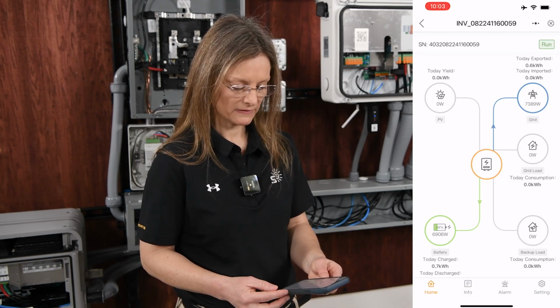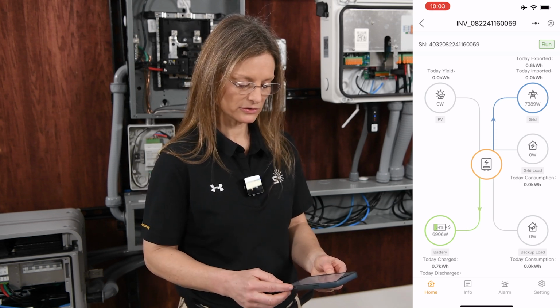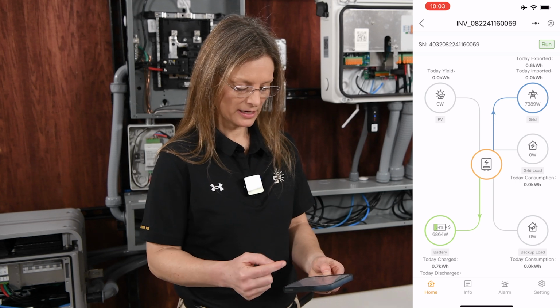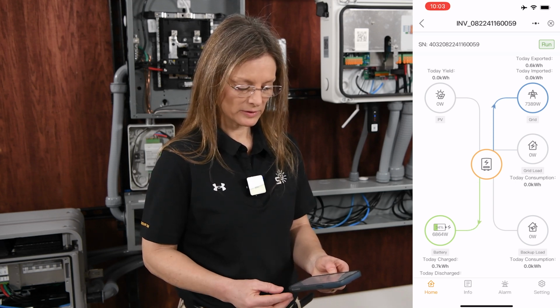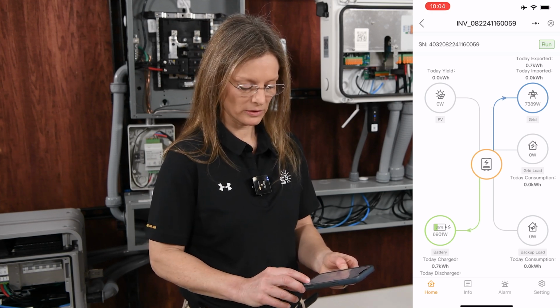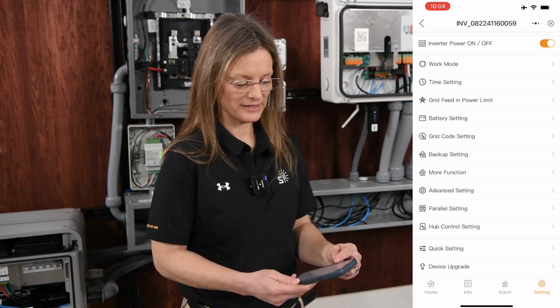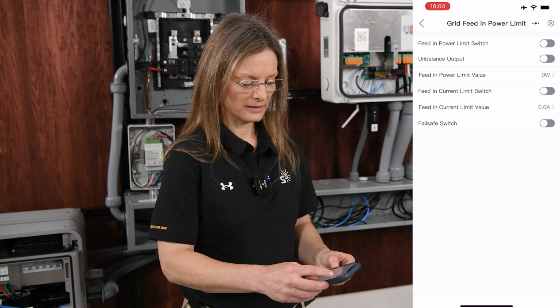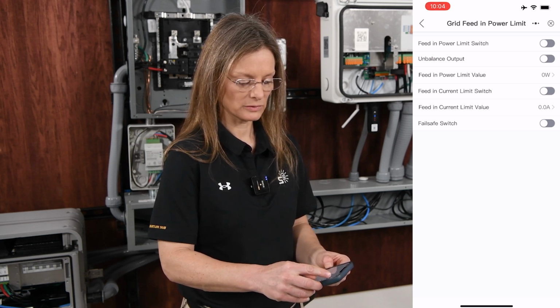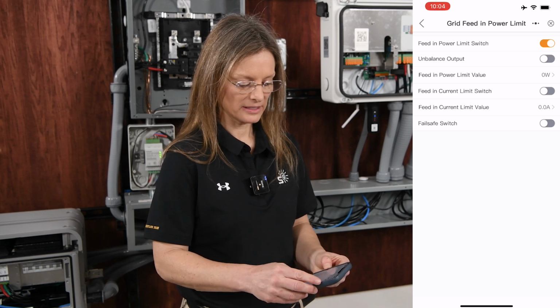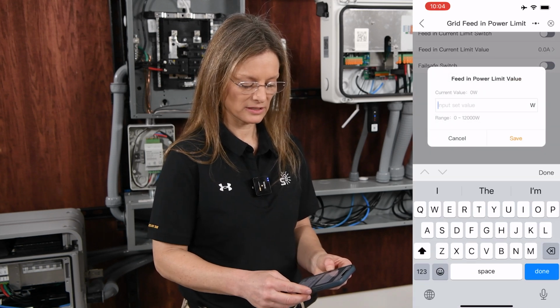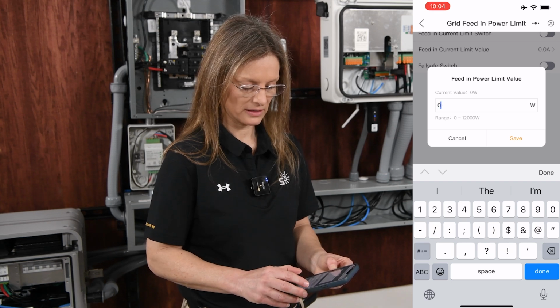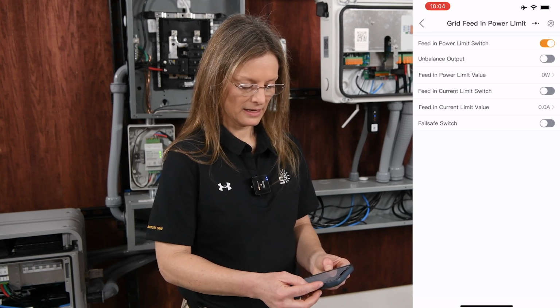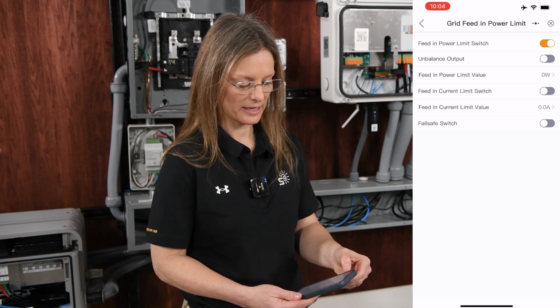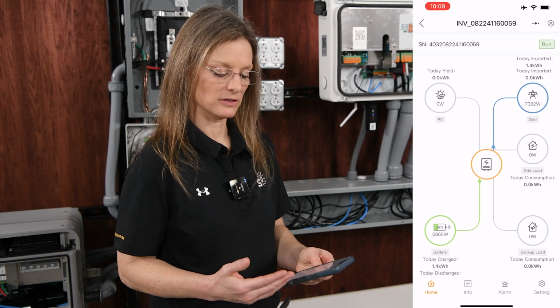So we're back to the home page now, and we see a nice animated graphic here that shows that our inverter is sending power back to the grid and sending power to charge our batteries. The next thing we need to do is limit our export power because we do not want to actually sell power back to the grid. So we will go to settings and we'll tap on this grid feed-in power limit. And the toggle switch at the top that says feed in power limit switch, we will turn that on. And it's already set to 0 feed in power limit value. If that was not set to 0, we could put in a 0 there and we could say save. And all of these other values can stay the same. We'll click the back button. Notice that we set our export power to be 0 export.